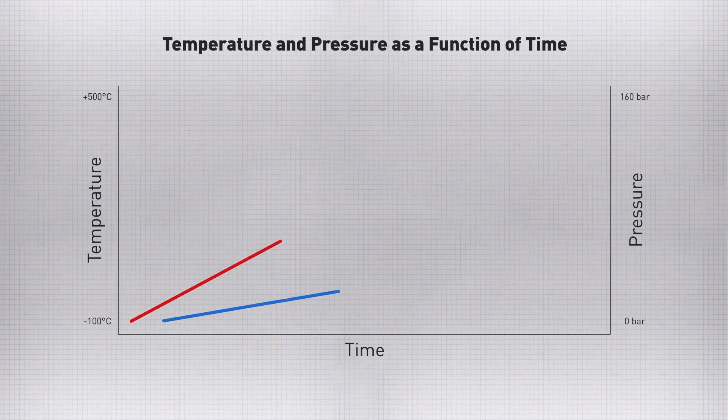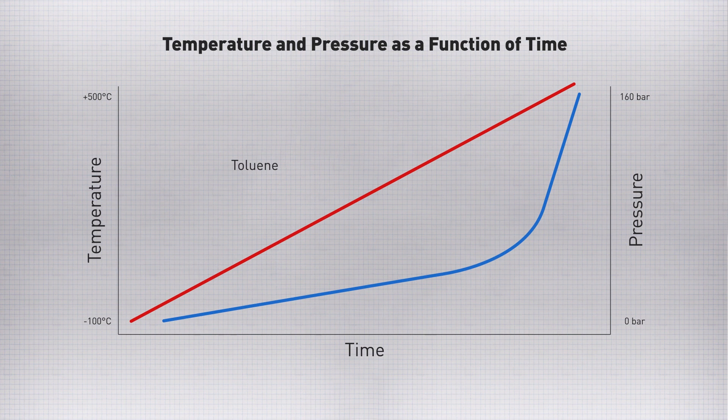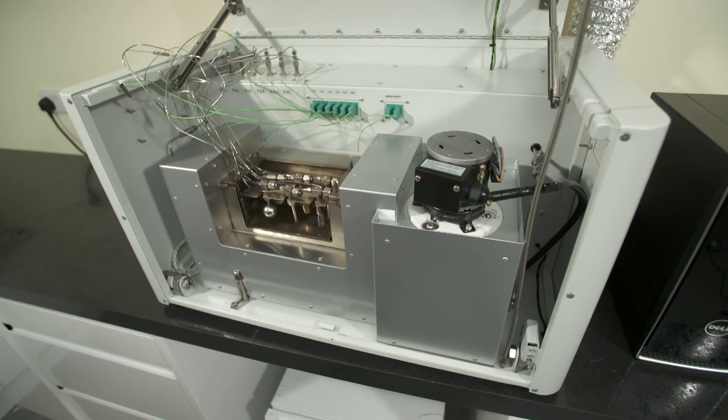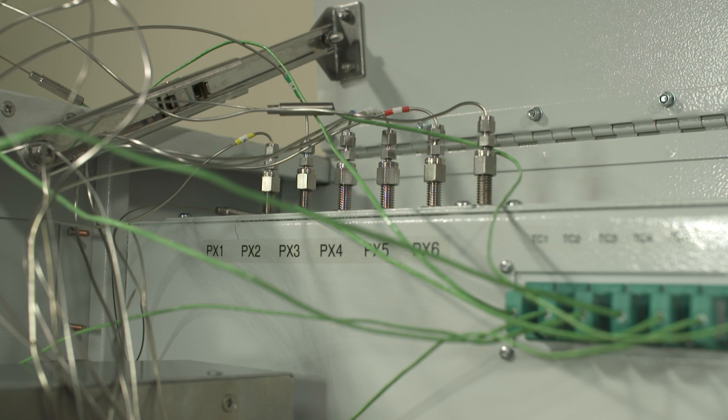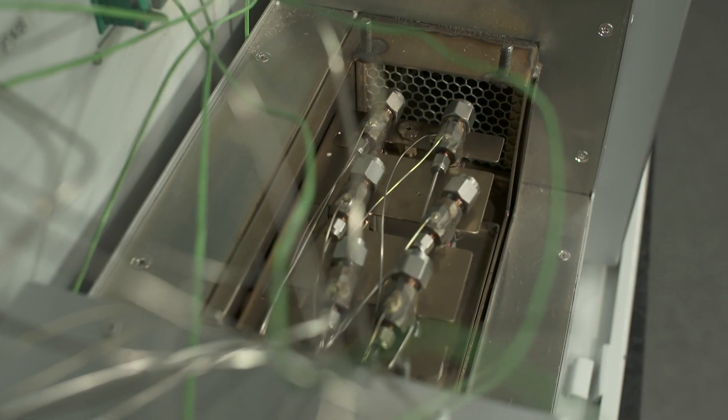Samples can be tested from sub ambient to 500 degrees centigrade with pressure range to 160 bar. The system is a rugged explosion proof design allowing both scanning and isothermal testing.